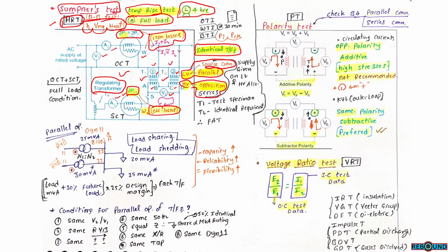So from this test only, we are able to get all the results of the open circuit test and all the results of the short circuit test at the same time. Here the supply is given on both LV and HV at the same time, so this condition is considered as full load condition. The open circuit test and short circuit test parameters we are able to get at the same time. T1 is the test specimen. T2 is the identical transformer which is required to perform this test. So this type of test can only be possible in factories, not at site condition.